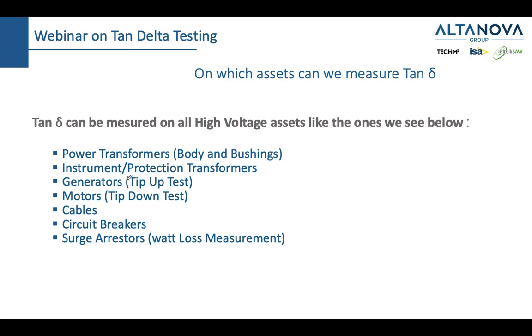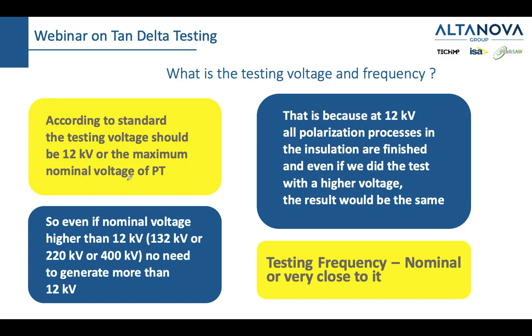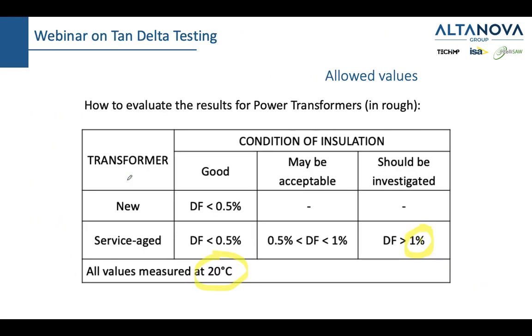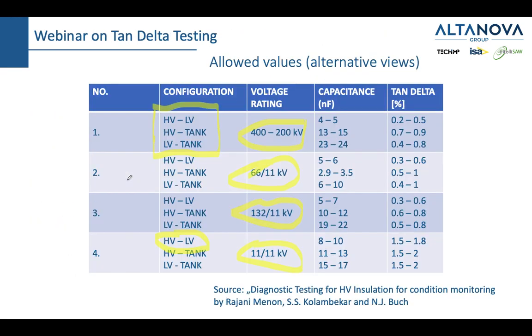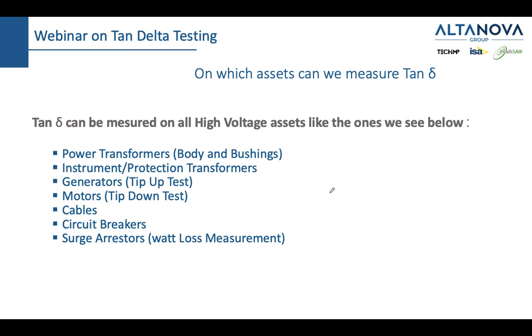And you do the same thing with a motor. On a cable, you can also test a power factor or a tan delta, and generally, on a cable, you will have much lower values. So again, to discern the values which we're talking about, these are the values for a transformer. If we were to talk about cables, then these numbers would be much smaller. And if we were to talk about generators, then these numbers would be much bigger. So for a generator, between 3 and 5%, that's a good value of a tan delta for a generator.